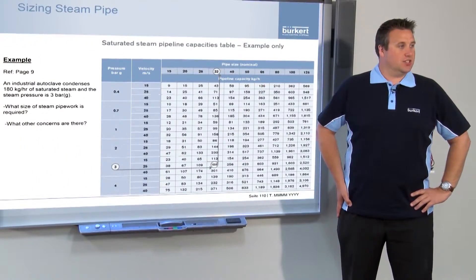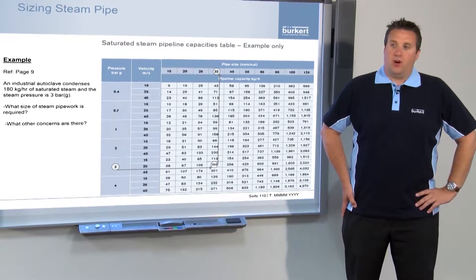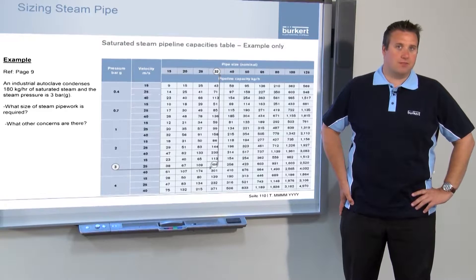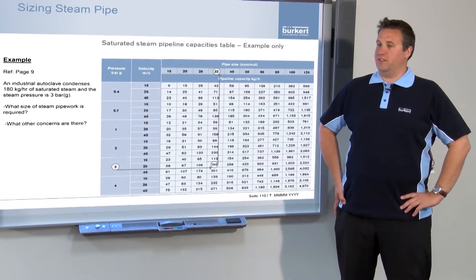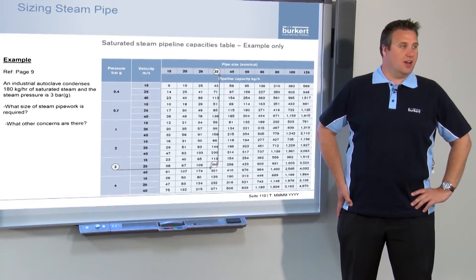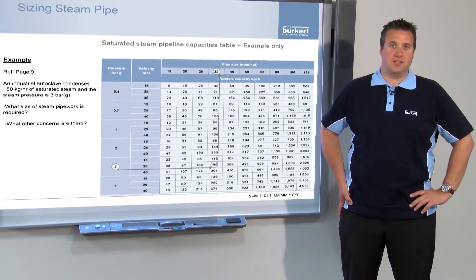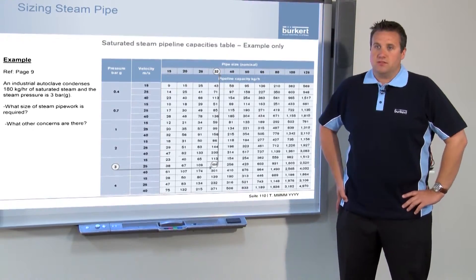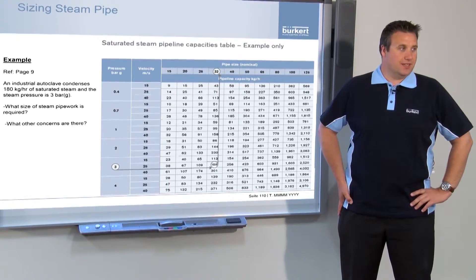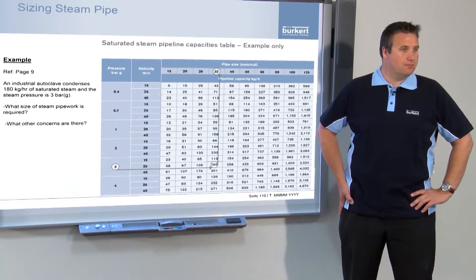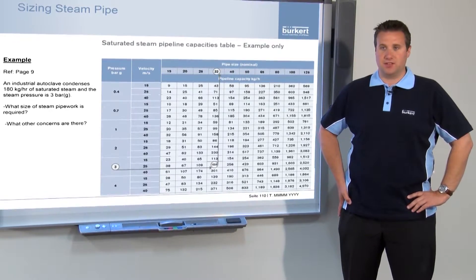We're now going to move on to how to size a steam pipe. For applications where we look at pipework less than 50 meters in length, we can use what we call the velocity sizing method. This is where we try to size the pipework using a steam velocity of around 25 meters per second. In practice, steam velocities can actually be between 15 and 40 meters per second, but the happy medium between both of these is the 25.